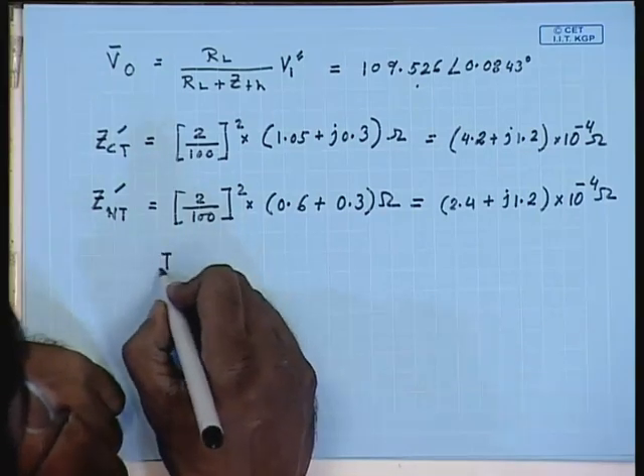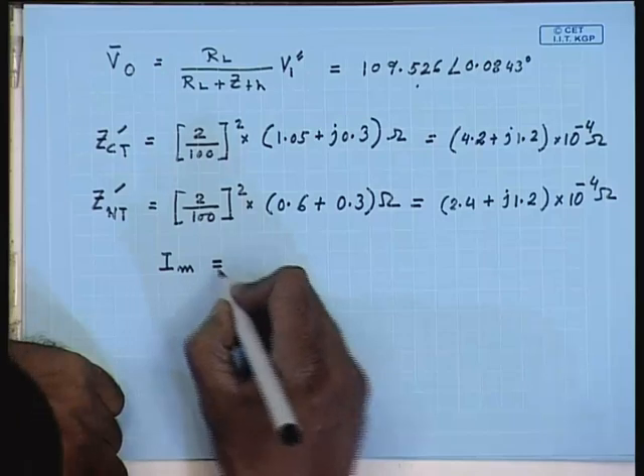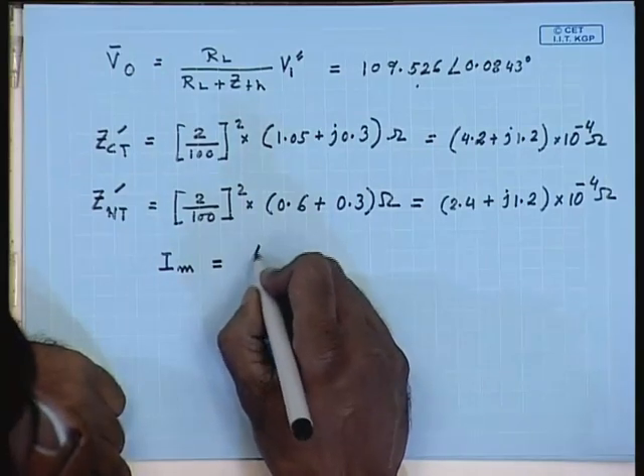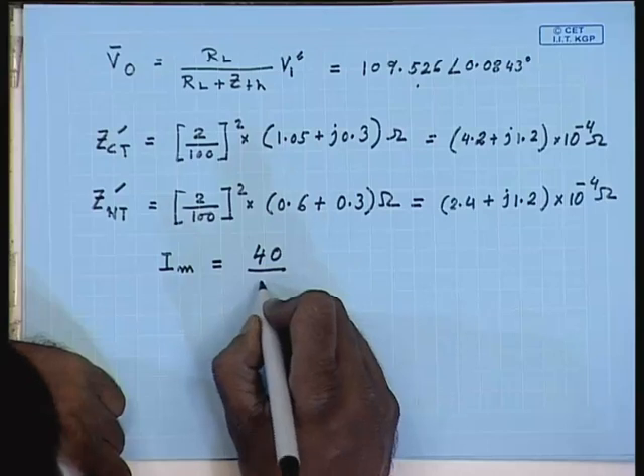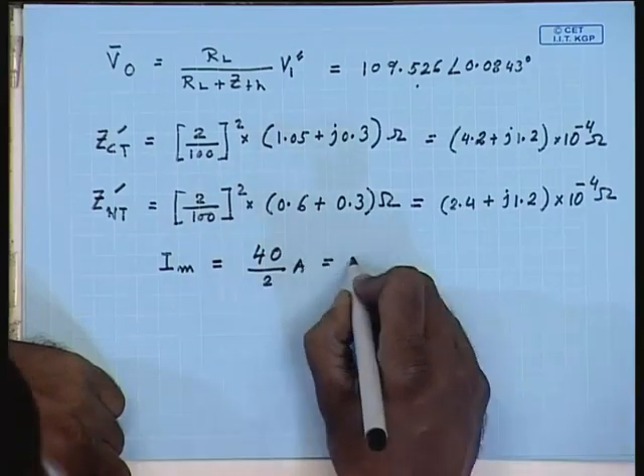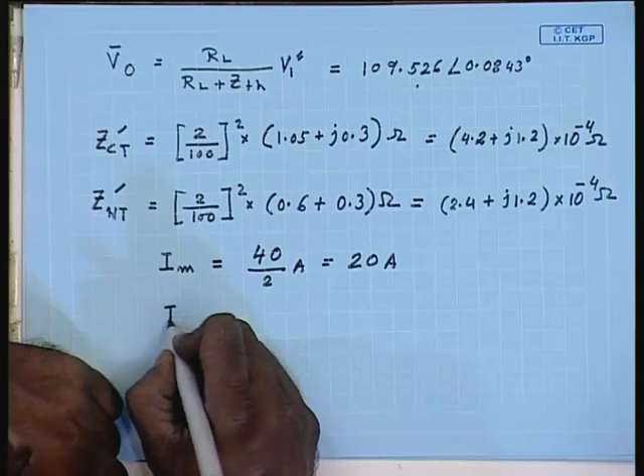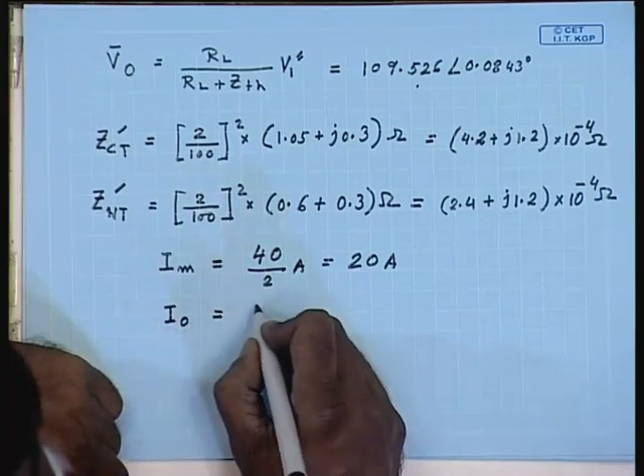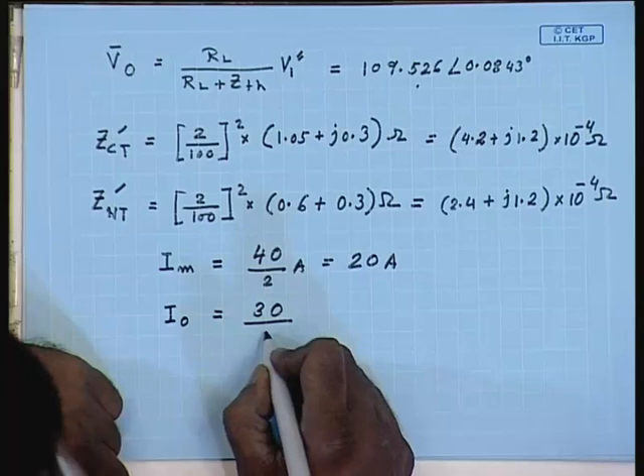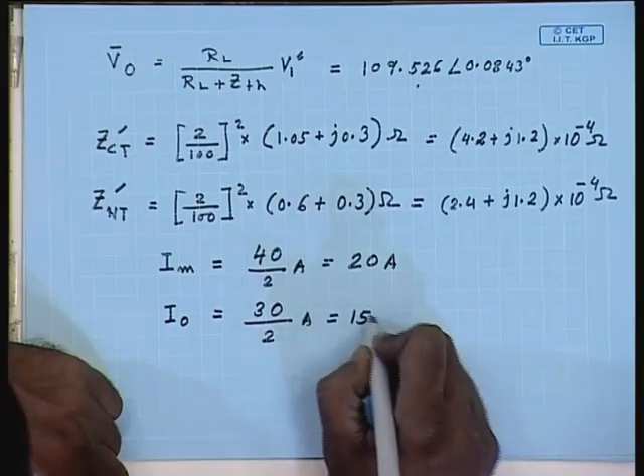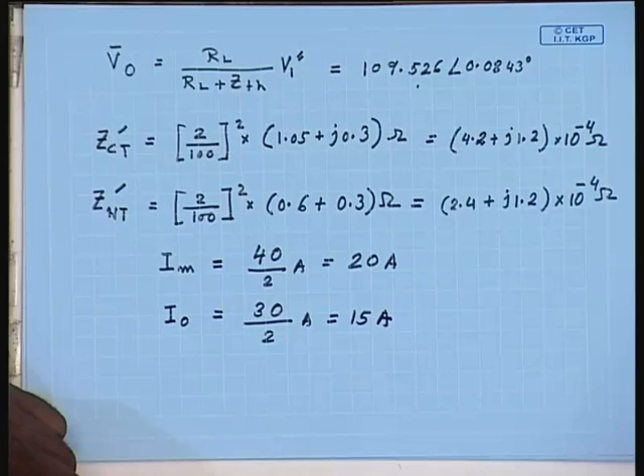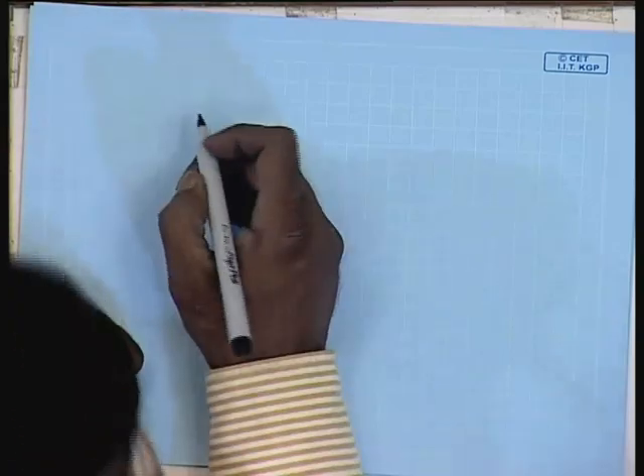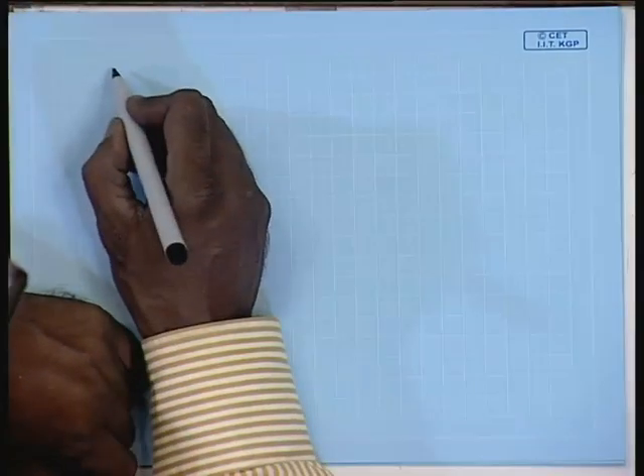The magnetization current referred to the supply side is magnetization ampere turns divided by turns on the supply side, 40 by 2. This will be equal to 20 amperes, and the iron loss current is 30 ampere turns by 2, that is equal to 15 amperes. So, the equivalent circuit of the CT looks somewhat like this.